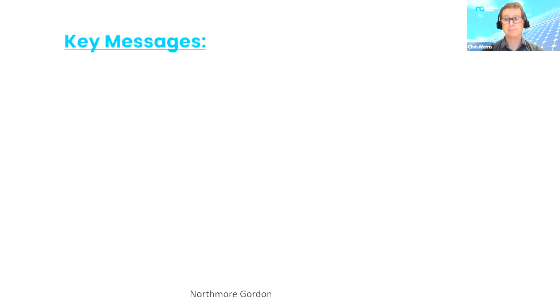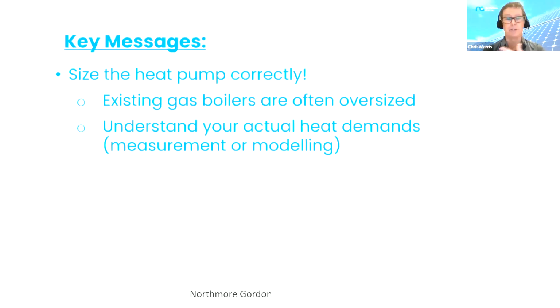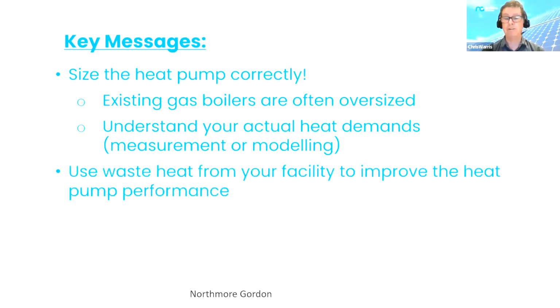So yes, the key messages we're going to repeat through this webinar in a bit more detail: size the heat pump correctly. Your existing gas boilers are probably oversized, so you need to understand your actual heating demands, whether by measuring your existing system or modelling it properly. Use the waste heat from your facility where you can to improve the heat pump performance.